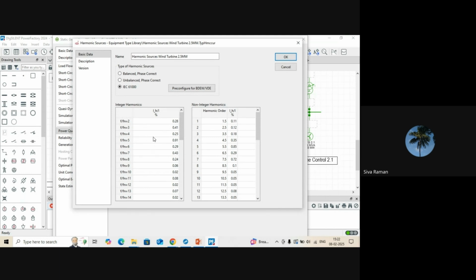The left bottom one is an integer. That is our harmonic value: second order, third order, fourth order. On the right side, it is non-integer, so it means 1.5 to 2.5. What does it mean? 1.5 means it is 75 hertz, so we are modeling from 75 hertz. So it is an interharmonic. This is an integer harmonic.